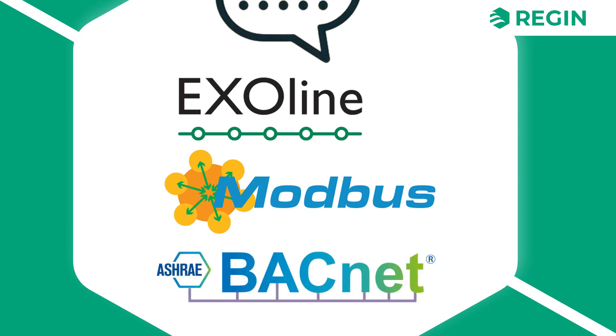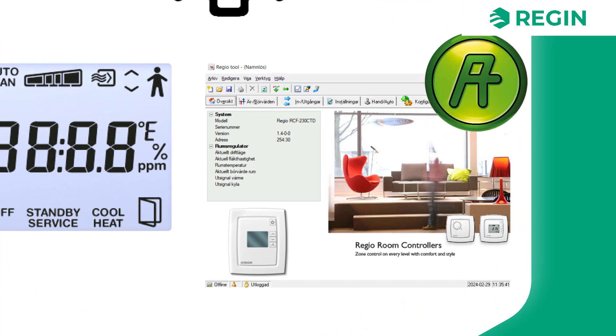The RCF communicates only over RS-485 serial, with support for three protocols: EXOline, Modbus, and Bacnet. It is configured either via the onboard display or via Regin's software Regio Tool, available for free from their website.